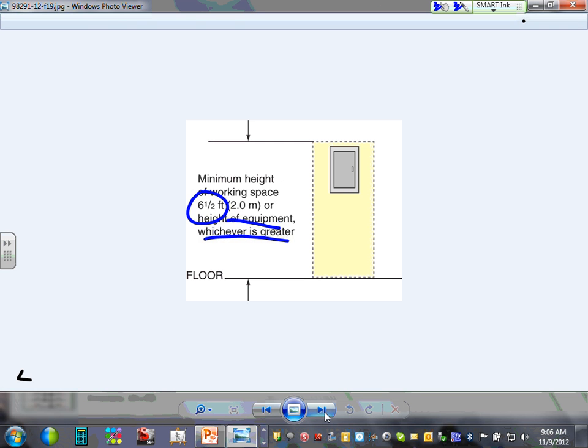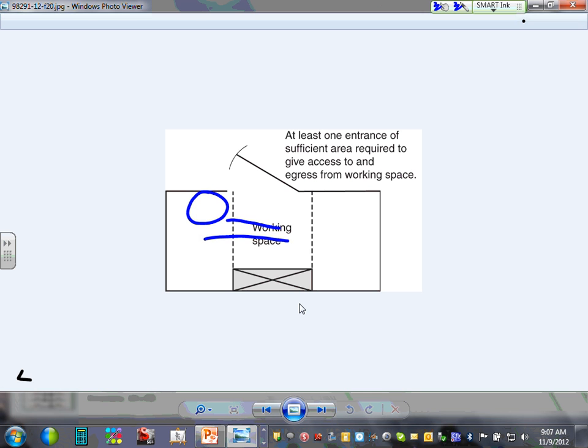If I have a switchgear, and my switchgear, guys, is 120 inches, the height has to go all the way up to the height of the switchgear. That place cannot be used for anything else, you can't put anything in it, because that's the working space around electrical equipment. Can I have thumbs up, Chad? Okay. So we talked about the width of the equipment or 30 inches, the height 6.5, or the height of the equipment, the depth from 3 feet all the way to 4 feet. So these are the 3 things that you guys need to know.